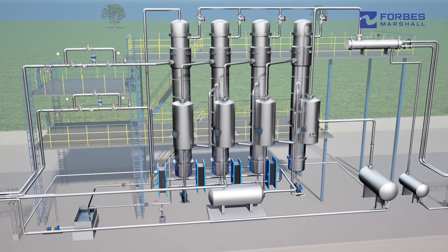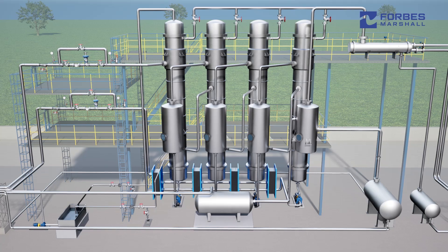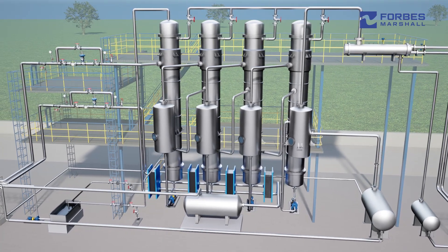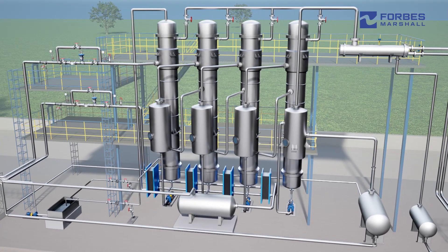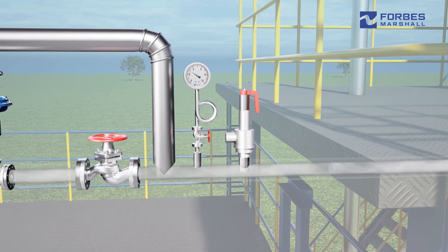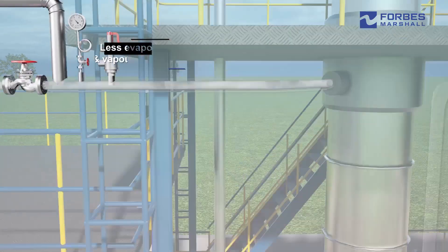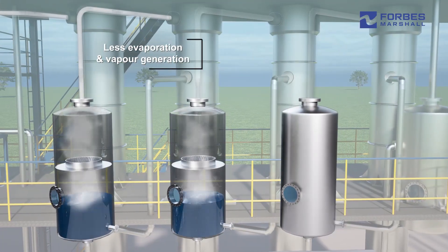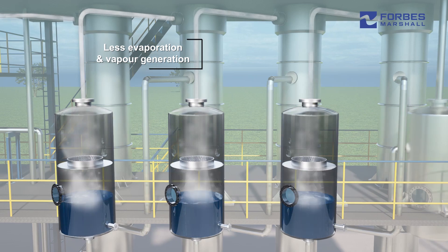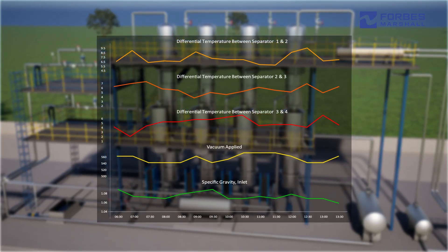Lower performance against design parameters can be attributed to conventional control philosophies, which fail to account for dynamic variations in actual conditions. For example, when steam supply pressure to the first effect fluctuates, it reduces vapor production, leading to less evaporation and vapor generation in subsequent effects, ultimately reducing overall evaporation.